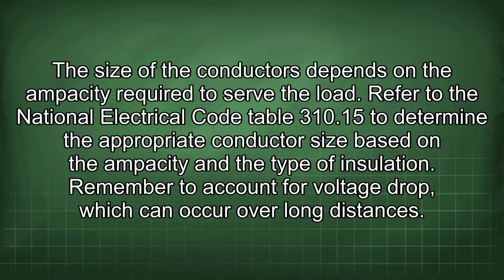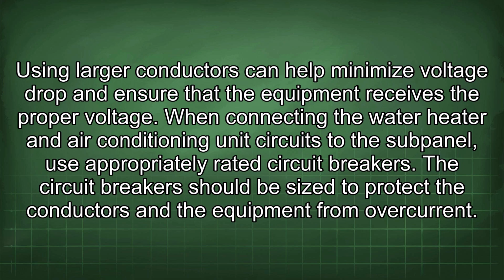The size of the conductors depends on the ampacity required to serve the load. Refer to the National Electrical Code Table 310.15 to determine the appropriate conductor size based on the ampacity and the type of insulation. Remember to account for voltage drop, which can occur over long distances. Using larger conductors can help minimize voltage drop and ensure that the equipment receives the proper voltage.